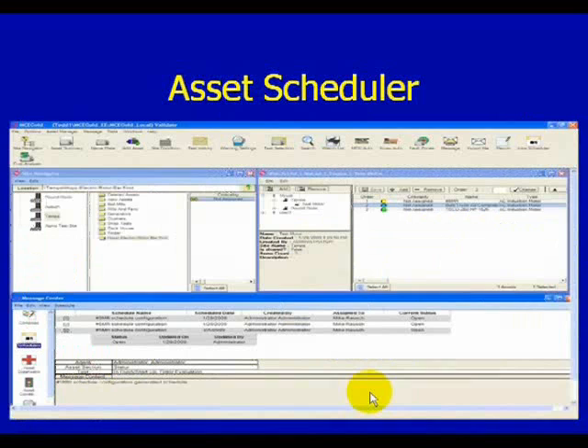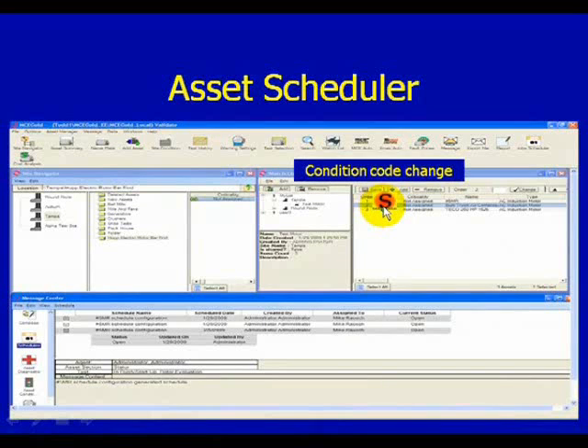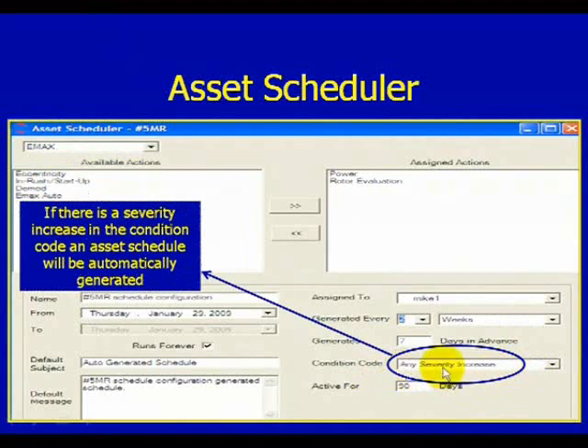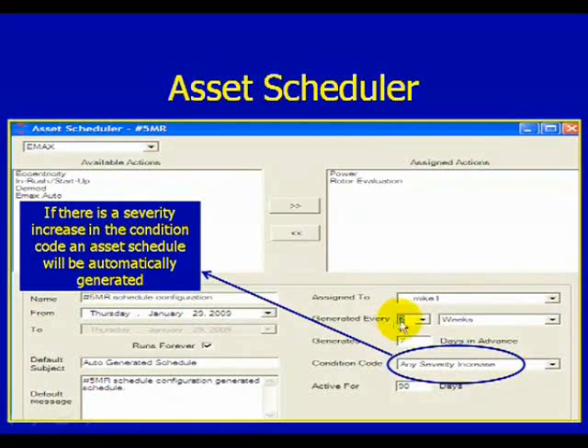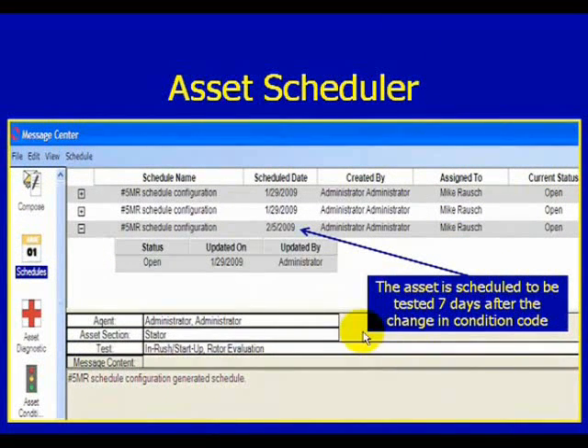Now, what happens if we change our condition code from caution to severe? As you can see here, we've changed the condition code from caution to severe. Automatically, we can see that in our Asset Scheduler, we have a place for any severity increase — we're going to generate a test request within two weeks of that severity increase and give a 7-day in advance notice. We go back to our message center and we can see that we've changed our condition code and generated a test to verify the condition of that asset based on the change in condition code.